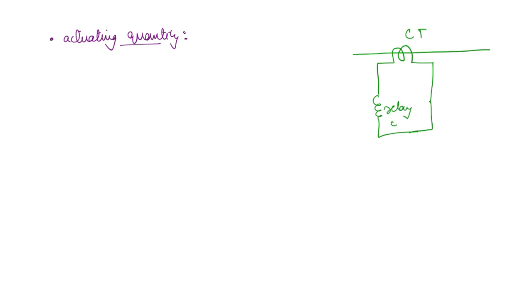First one is the actuating quantity. If you remember in the previous example, we had the main transmission line like this, and here we had the CT. When there is a fault, current will flow in the CT and eventually in the relay coil. So here the actuating quantity is the current, because of which the relay coil is getting activated. Sometimes it will be in the form of voltage. So the actuating quantity can be the current or voltage that is fed to the relay so that it operates.